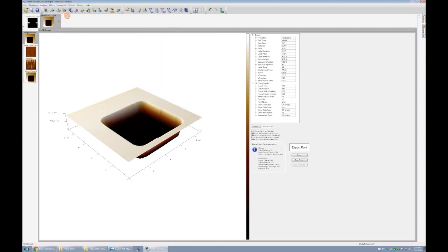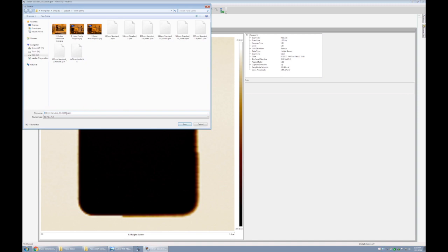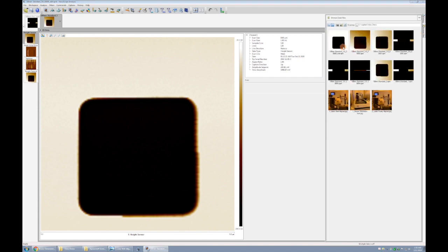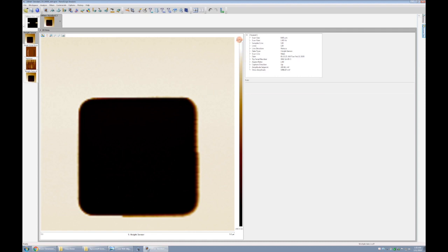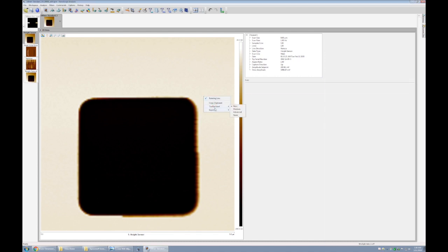In a lot of these different places, you can, say, go to your 2D image. You can right-click and export the screen display, but that's actually not great because it's going to give you the pixels on your screen rather than the pixels that you scanned. So if you want the pixels that you scanned, my recommendation would be to file save as and make some kind of copy of it, so we can call it an edit. And then in your browse files, we can find our edit, and then if you right-click and export as a TIFF, now you're exporting as an 8-bit color or 8-bit grayscale or 16-bit grayscale, and that will be the exact number of pixels that you have in your image. So this is something I'd recommend: make some nice whole numbers on your scale or modify your color scale in any other way, and then again do your export in this way rather than just a simple export like this.